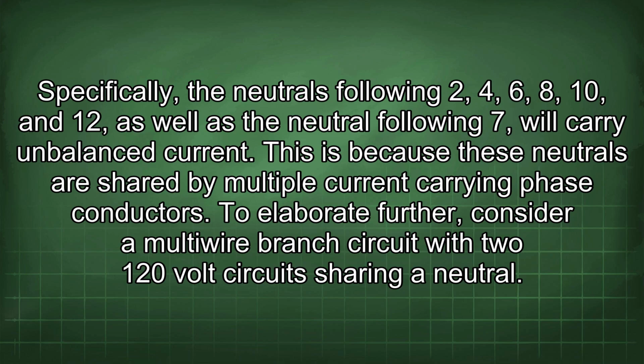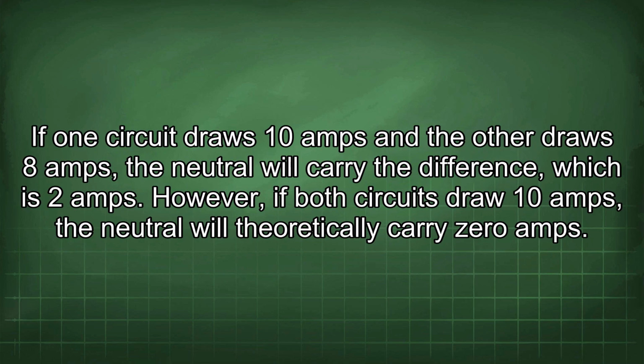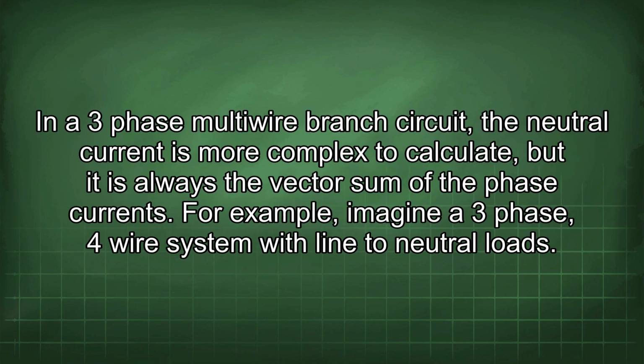To elaborate further, consider a multi-wire branch circuit with two 120-volt circuits sharing a neutral. If one circuit draws 10 amps and the other draws 8 amps, the neutral will carry the difference, which is 2 amps. However, if both circuits draw 10 amps, the neutral will theoretically carry 0 amps. In a 3-phase multi-wire branch circuit, the neutral current is more complex to calculate, but it is always the vector sum of the phase currents.